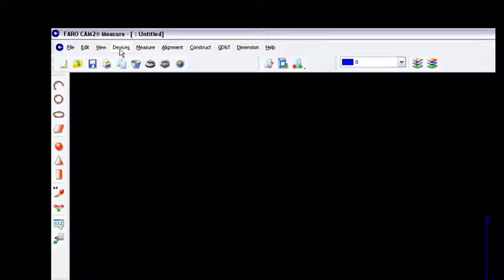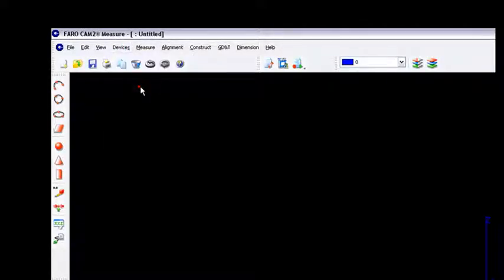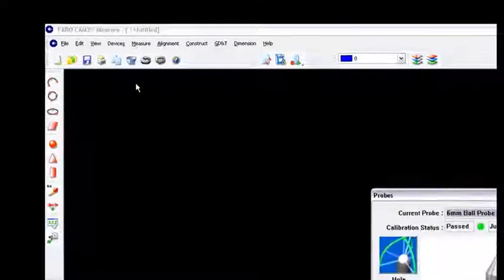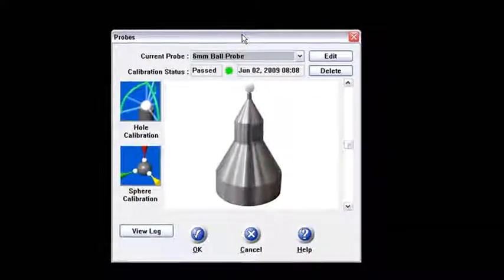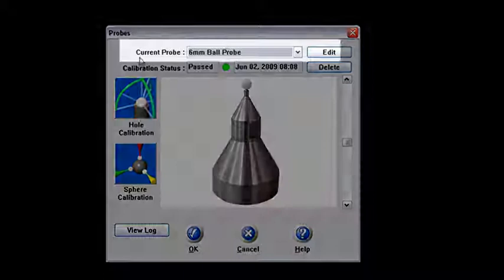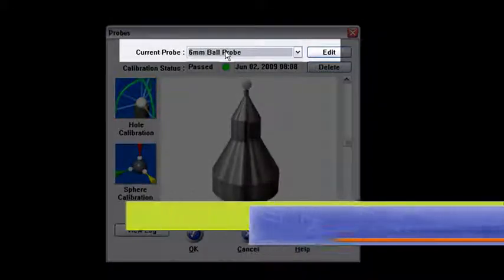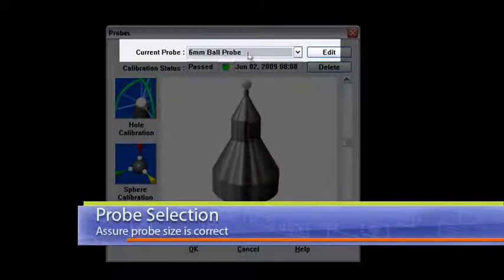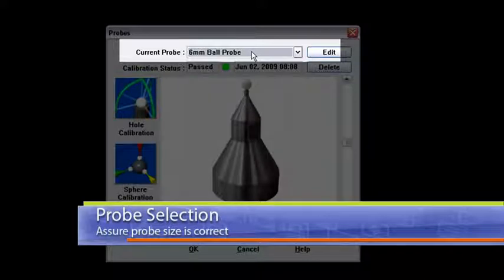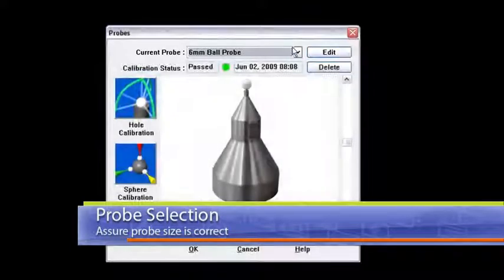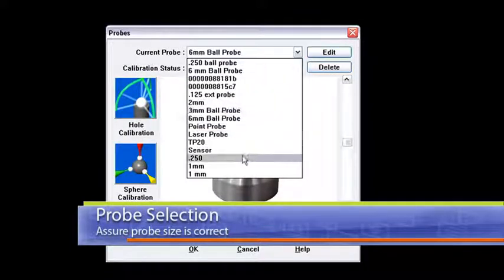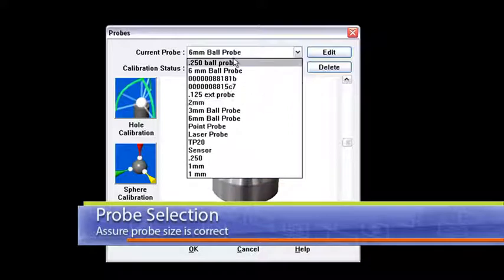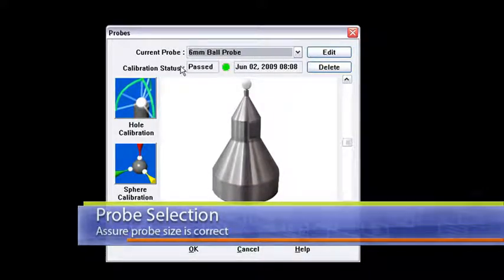I'm going to go under the Devices menu and then under Probes. Once I click on that, I get this Probes menu right here. The first thing to do is make sure that you've got the current probe set to the 6mm probe which is listed on the side of the probe. The other thing I wanted you to notice is there's a lot of other probe options underneath here. So make sure that you're on the right probe selection.